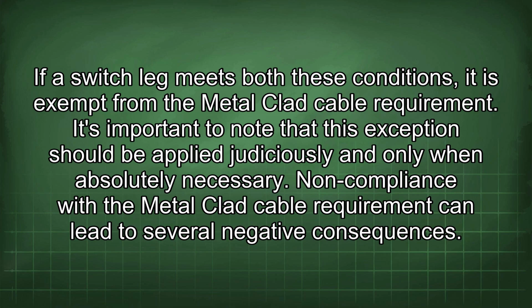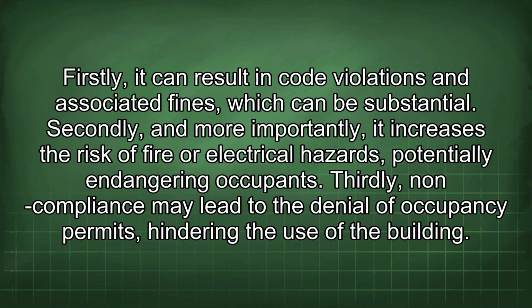Non-compliance with the metal-clad cable requirement can lead to several negative consequences. Firstly, it can result in code violations and associated fines, which can be substantial. Secondly, and more importantly, it increases the risk of fire or electrical hazards, potentially endangering occupants. Thirdly, non-compliance may lead to the denial of occupancy permits, hindering the use of the building.